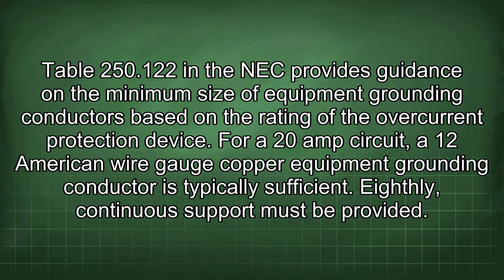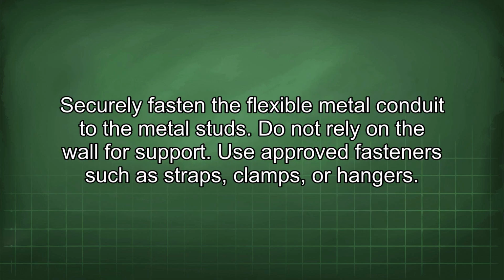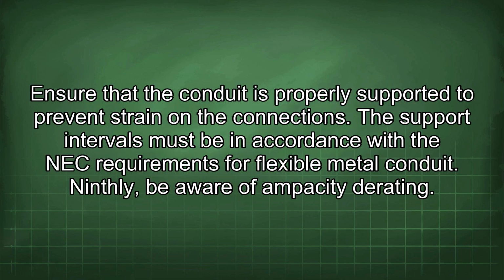Eighthly, continuous support must be provided. Securely fasten the flexible metal conduit to the metal studs. Do not rely on the wall for support. Use approved fasteners such as straps, clamps, or hangers. Ensure that the conduit is properly supported to prevent strain on the connection. The support intervals must be in accordance with the NEC requirements for flexible metal conduit.